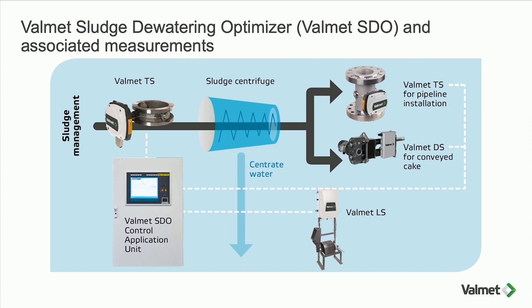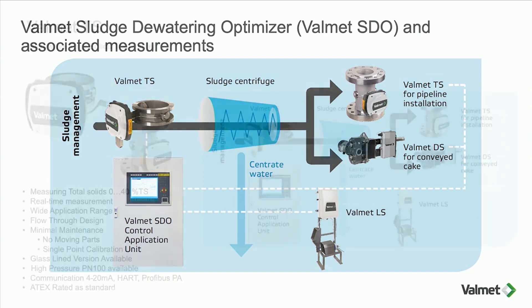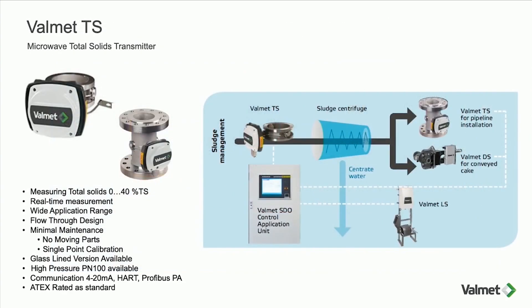Looking at the measurement technology itself: this is a product called Valmet TS, designed to measure right through the wastewater process from primary thickening through to centrifuge. It has a wide measurement range — zero to forty percent total solids. It's normally installed on the inlet of the centrifuge, but because it can measure quite high solids, it can also measure in the dry cake area if you are pumping the dry cake through a pipe.